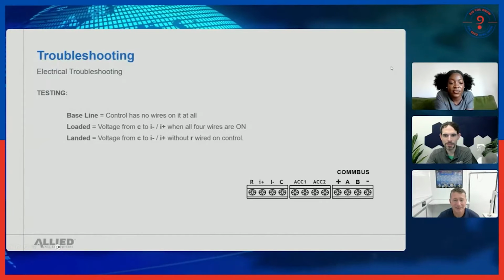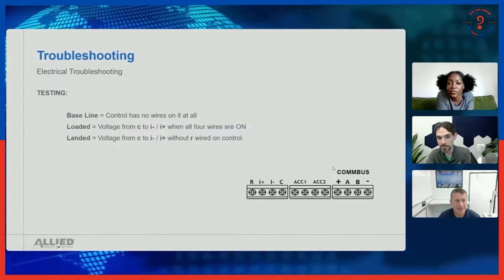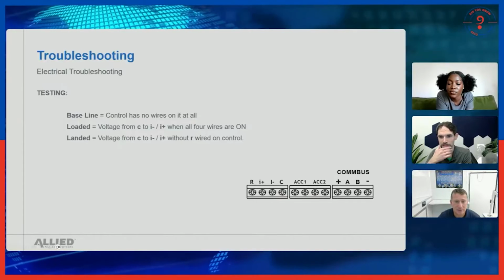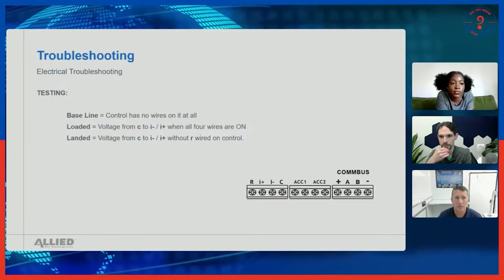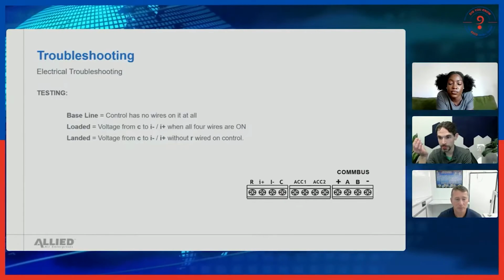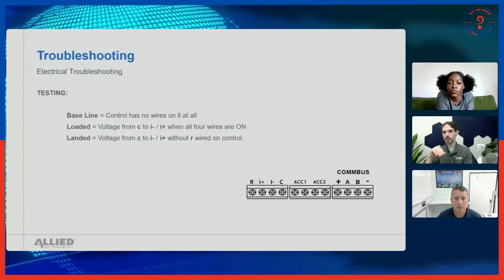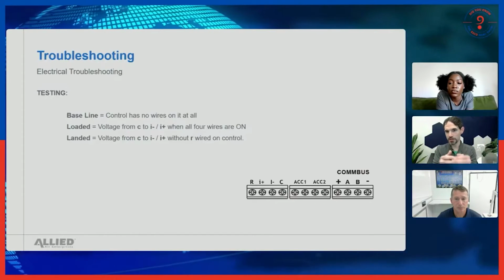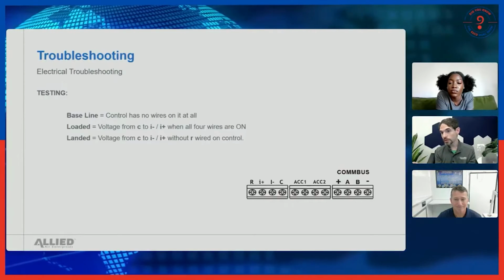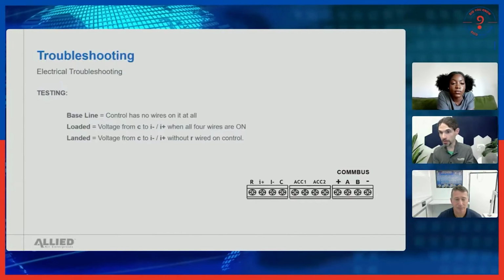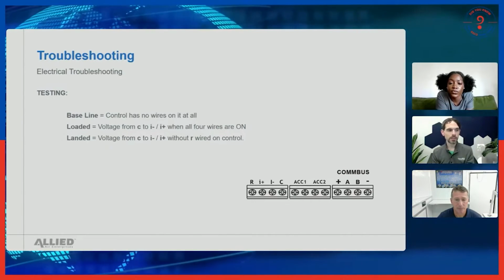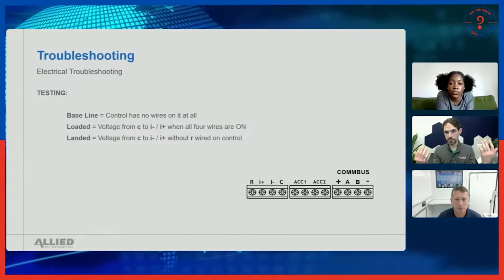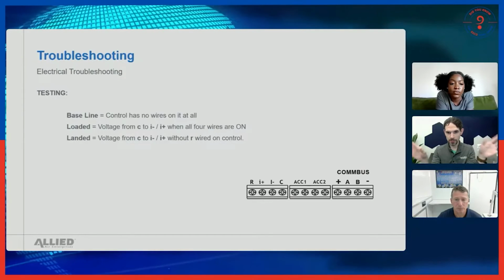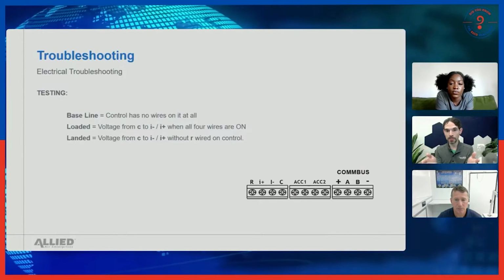Yeah, and there, I'll tell you what, we'll jump right into that one, won't we? So if we keep looking at the connections themselves, there's kind of three things we can walk through, starting off with the wires themselves. So again, looking at everything around, we think we're good, we think we've got good connections. You can't see through the walls, so you don't know what's happening between point A and point B all the time. There could be other things in the way. So what you do, some of the tests you start off with is taking everything out of the system, power disconnect included, and you're just looking at the wire itself.